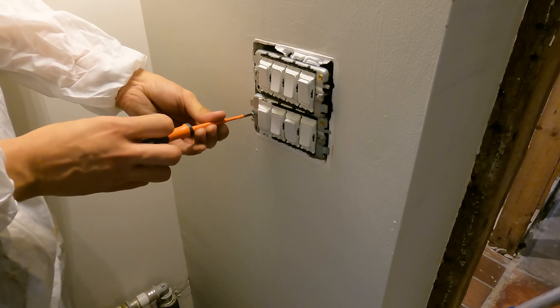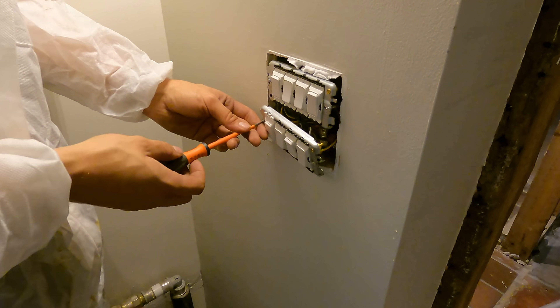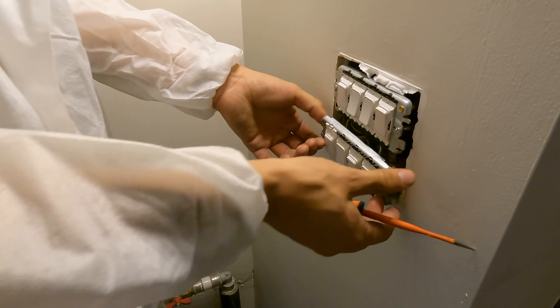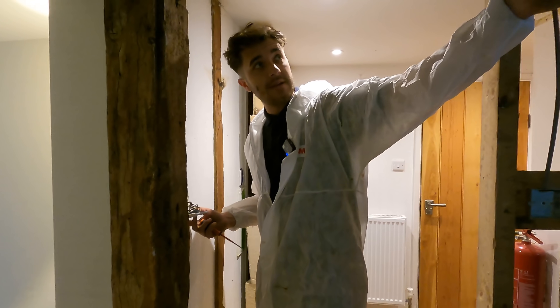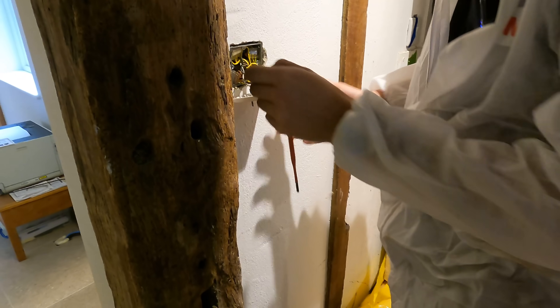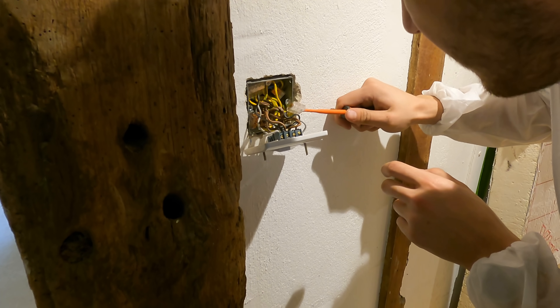So let's see what's inside these switches. This switch was supposed to be a two-way for some lights on the other side of the hall, but it's not doing anything and I can see there's nothing connected there. I'll have a look and see if the cable has maybe been brought through but not connected, or if it's just not been put through at all. That's some horrendous wiring on the other side of this wall. The cable is connected up this side but not connected up on the other side. This is for the spotlights that needs a two-way.